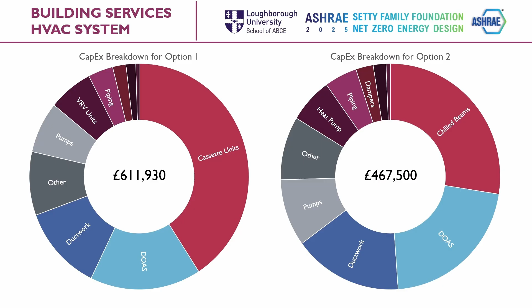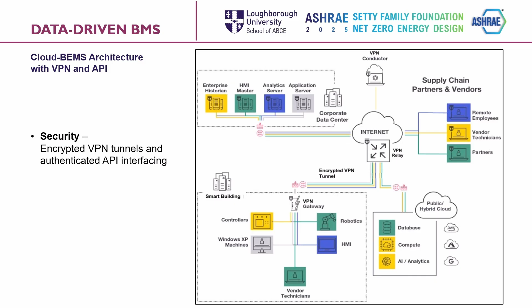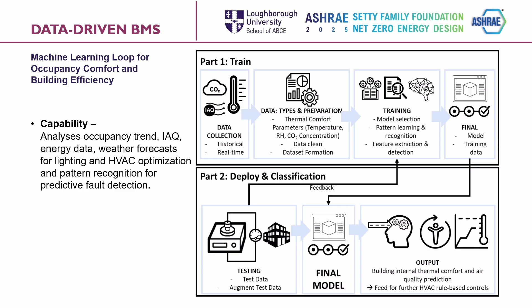In our building, the BMS isn't just a control system, it's intelligent. A cloud-based machine learning model is integrated that connects securely to the BMS through encrypted VPN tunnels and authenticated API interfaces. This model doesn't just react, it predicts. It analyzes occupancy trends, indoor air quality, energy data, and weather forecasts to proactively optimize the lighting, HVAC performance, and set point schedules. Beyond optimization, the system also handles data-driven fault detection. Unlike conventional alarms, it uses pattern recognition to detect HVAC issues before they cause failures, saving time, reducing spare parts stock, and keeping our critical environments running smoothly.